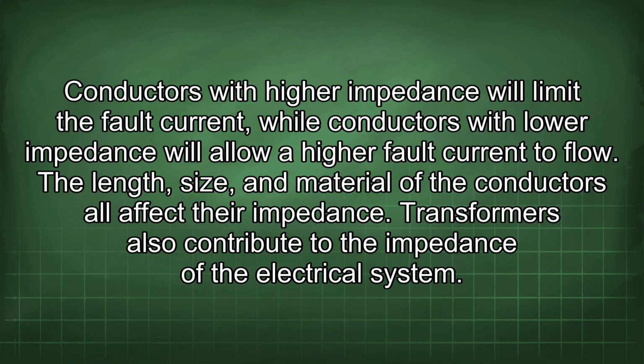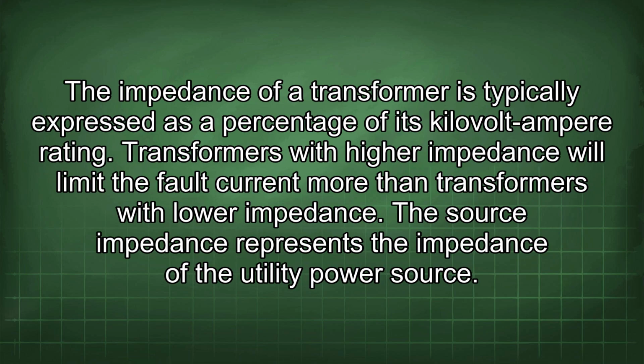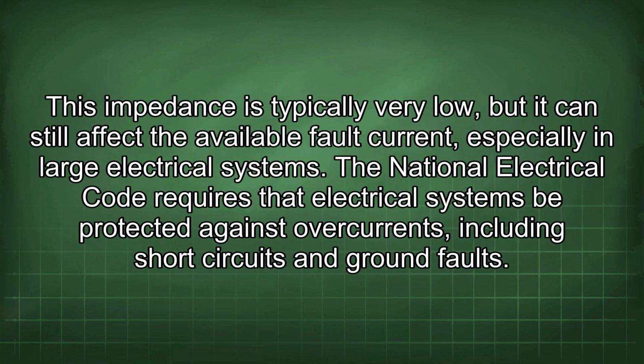Transformers also contribute to the impedance of the electrical system. The impedance of a transformer is typically expressed as a percentage of its kilovolt-ampere rating. Transformers with higher impedance will limit the fault current more than transformers with lower impedance. The source impedance represents the impedance of the utility power source. This impedance is typically very low, but it can still affect the available fault current, especially in large electrical systems.